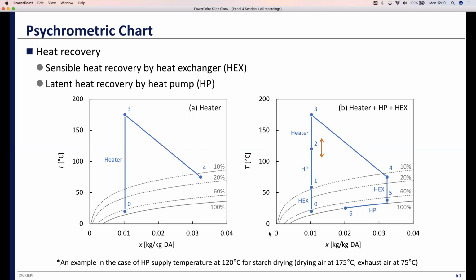Next, the right chart shows the heat recovery system. The heat exchanger recovers the sensible heat of the exhaust air from state point 4 to state point 5. Then, the heat pump recovers mainly latent heat from state point 5 to state point 6. We can see the exhaust air at state point 6 approaches the ambient state point 0. And the heat recoveries can reduce the heat load of the heater from state point 2 to state point 3. In this study, the heat pump supply temperature of state point 2 is changed, and we investigate the optimum point.